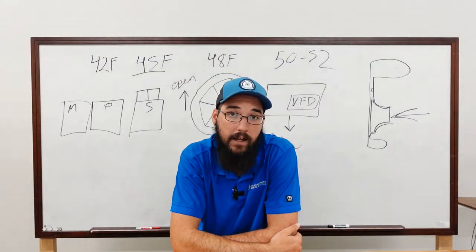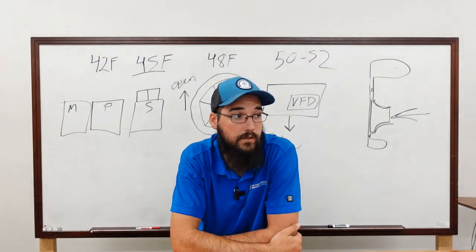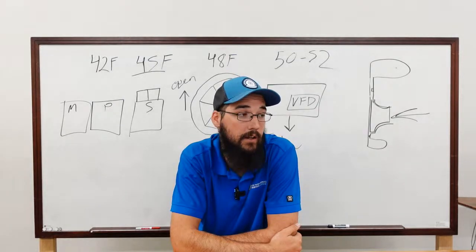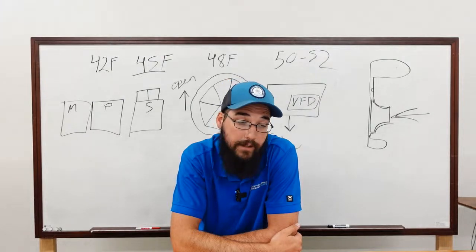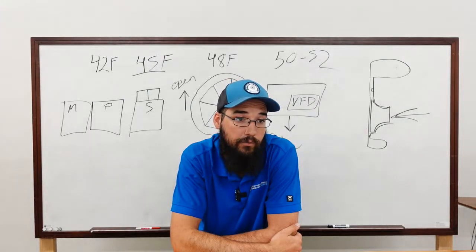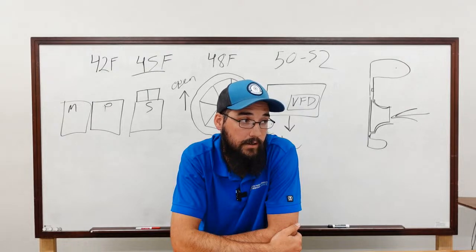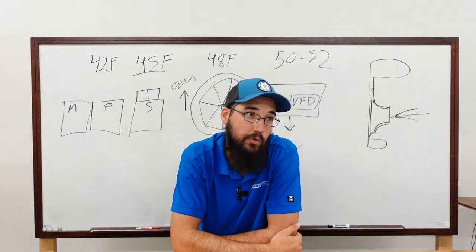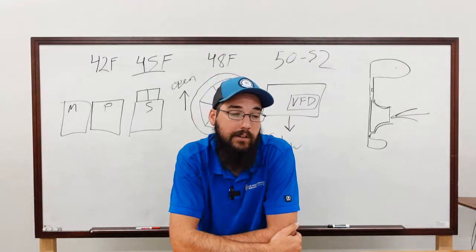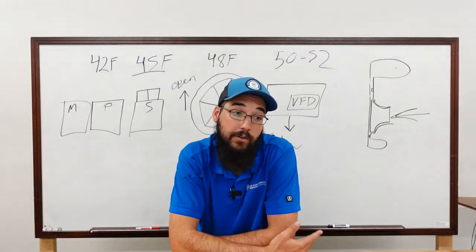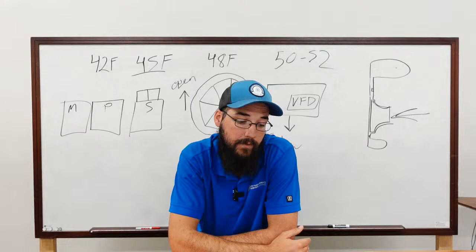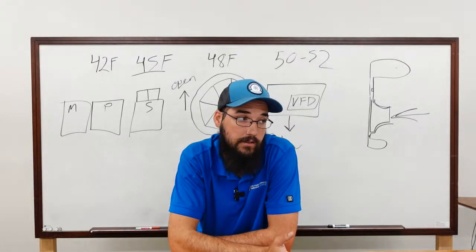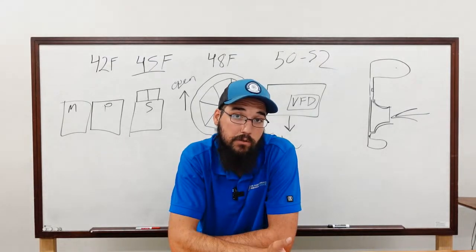Run that limit down. You probably won't get this system to run at capacity. And so that 45 degree set point is a dream and a dream only. But 50-something degree water and a cool-ish building, in server rooms that are not over temping, is better than no cooling at all. And the machines will run at that state.